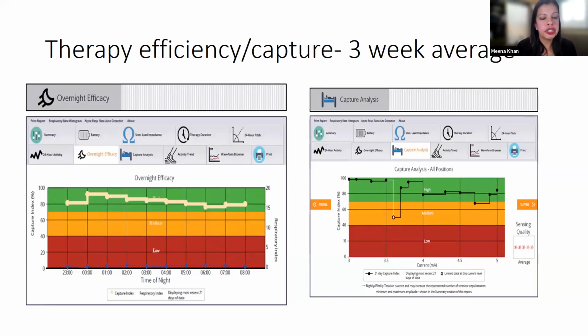And again, we look at capture. You can look at them individually per night. You can also look on average, and you can see, are they getting the high capture, at what times of night is their capture high? And then also you can see what milliamp they tend to be capturing on, and use that as a gauge of whether or not you need to adjust your range.